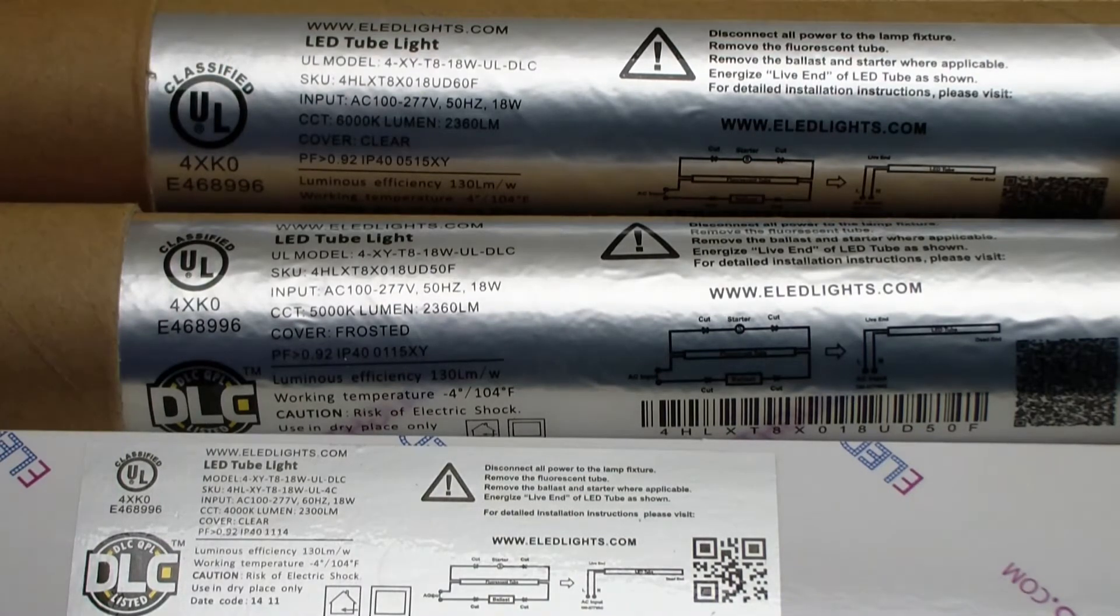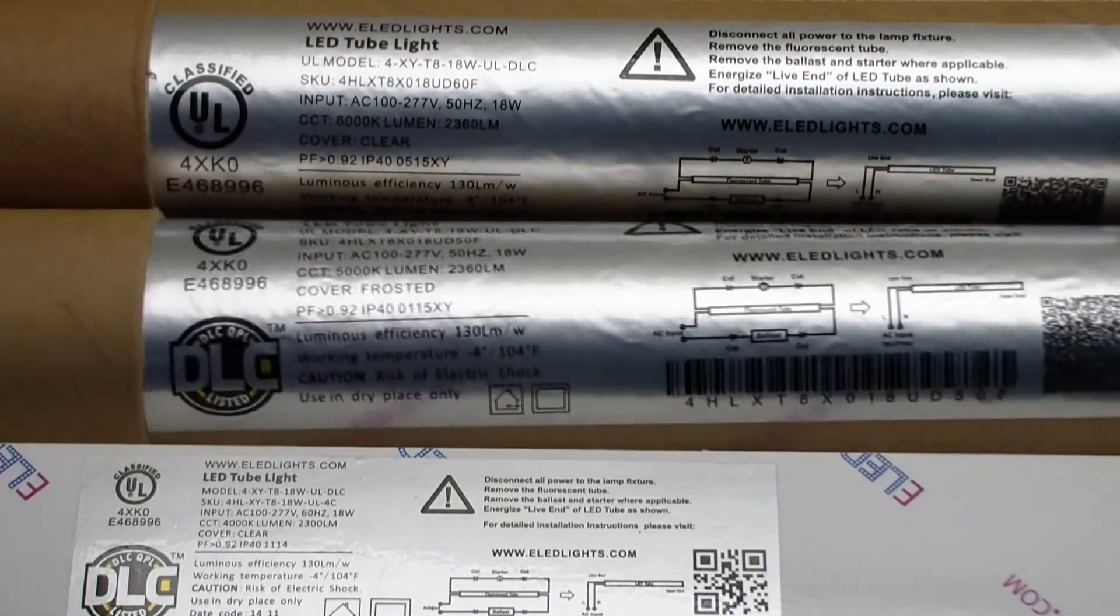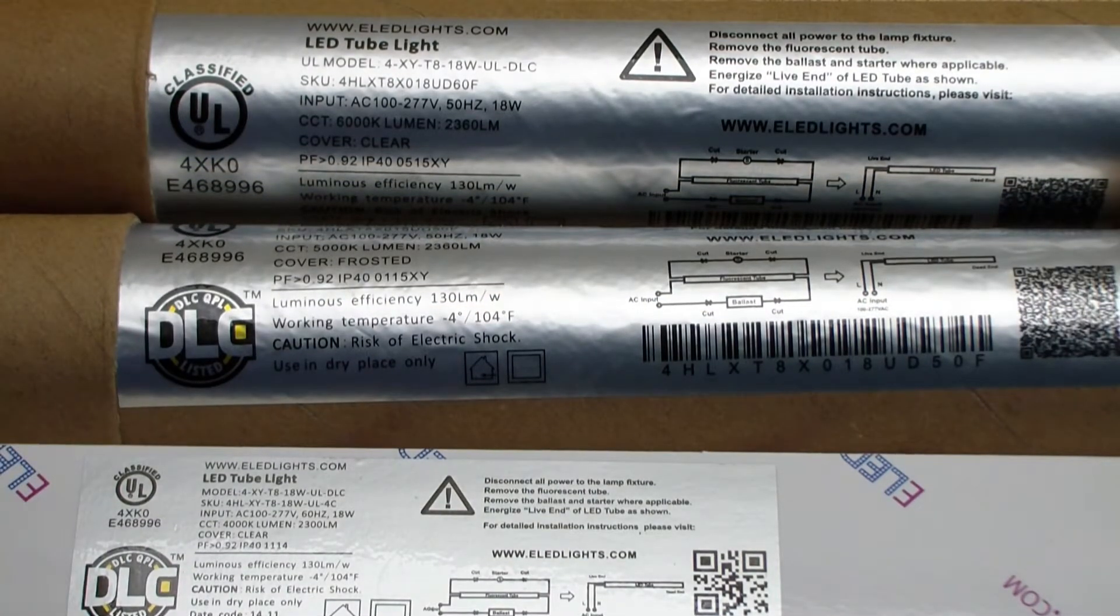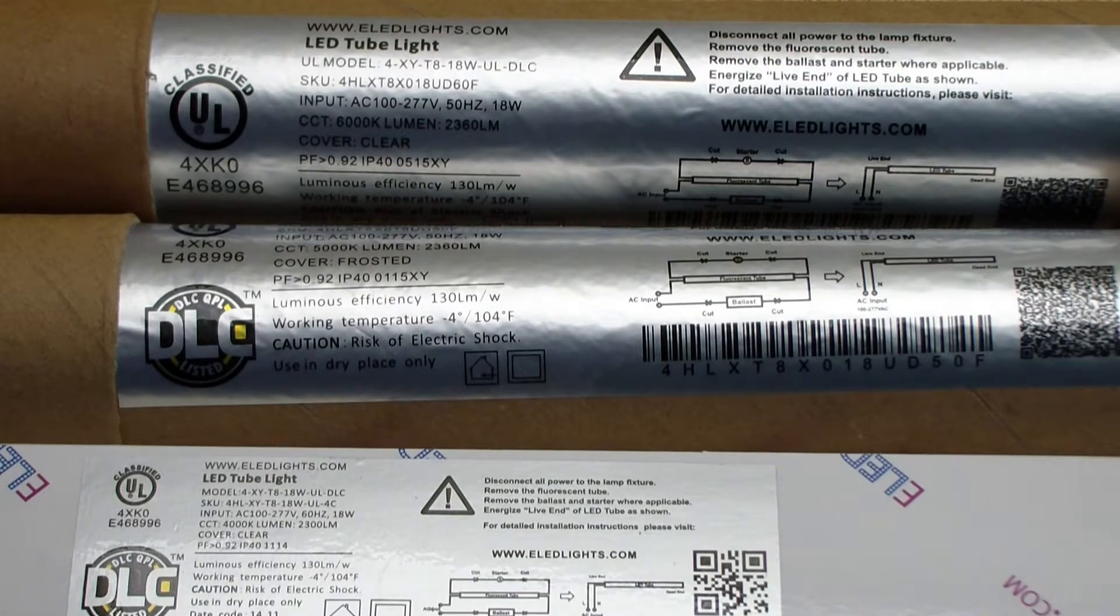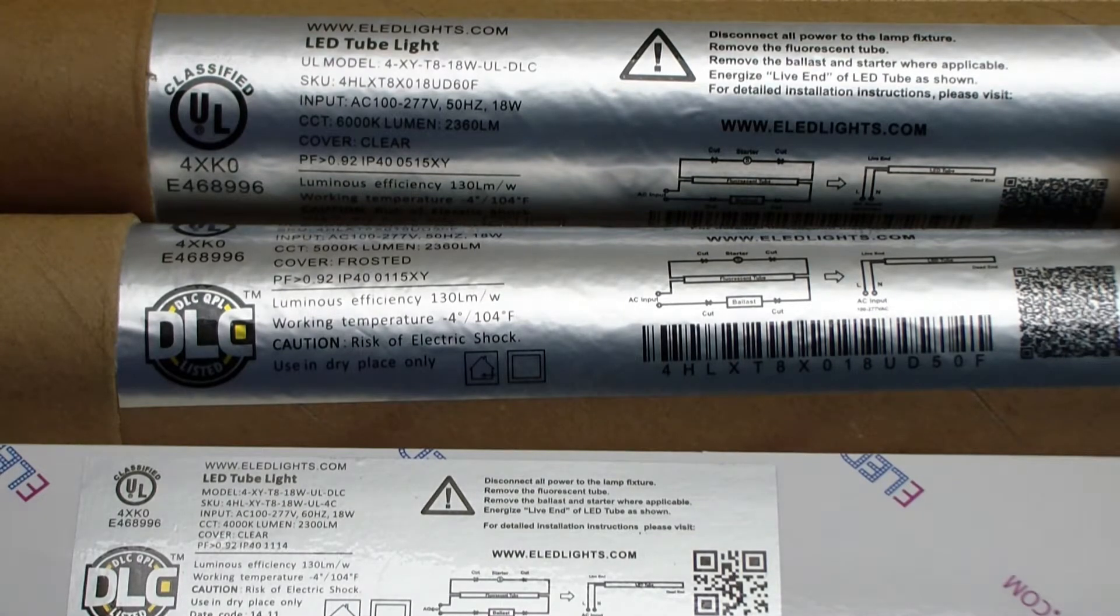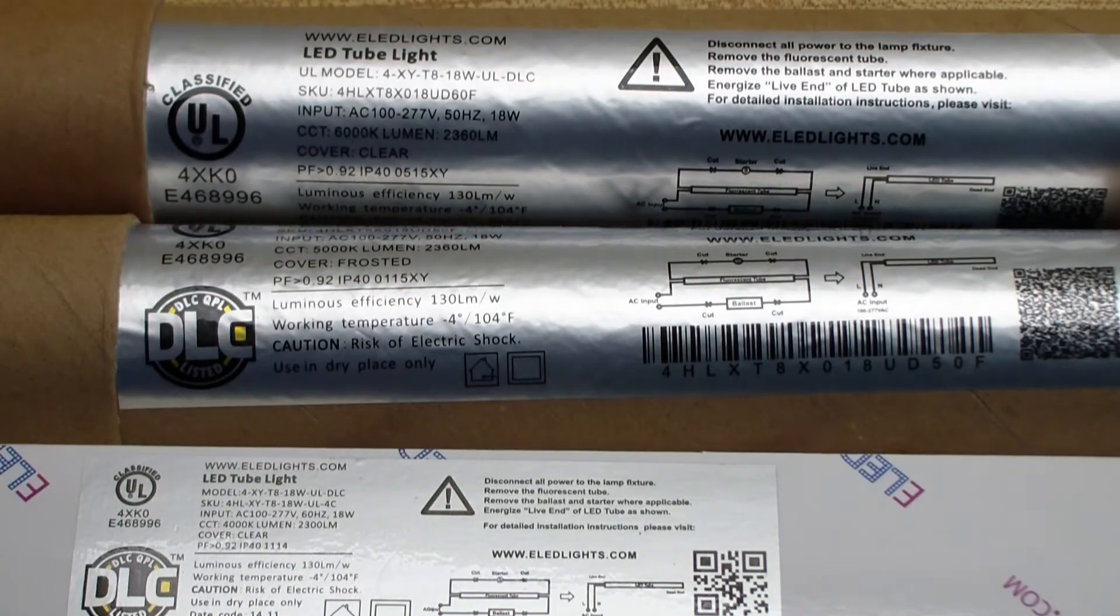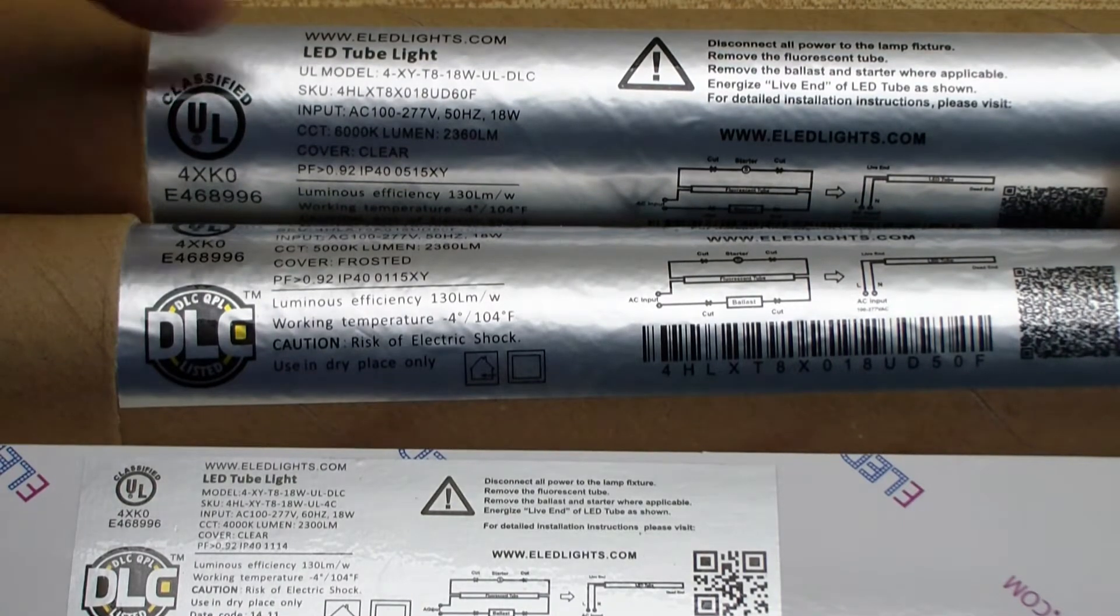Now one thing you'll notice is this DLC model that's 6,000 K doesn't have the DLC sticker. You can see the DLC logo. This is for the Design Light Consortium, and that means these things are rated by the consortium to meet their specifications. I was looking at the designlights.org website, and in order to meet their specification, you have to be below 5,000 K. So since this is a 6,000 K unit, it can't meet the thing. So it's kind of a little typo that has DLC in here, and it's also a frosted bulb that says clear.